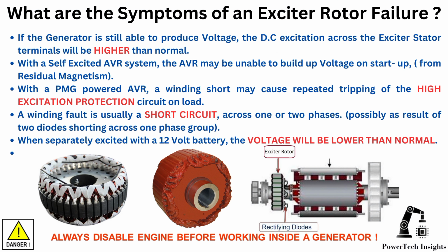Let's get started. Possible symptoms of an exciter rotor failure. If the generator is still able to produce voltage, the DC excitation across the exciter stator terminals will be higher than normal. With a self-excited AVR system, the AVR may be unable to build up voltage on startup from residual magnetism. With a PMG-powered AVR, a winding short may cause repeated tripping of the high excitation protection circuit on load.